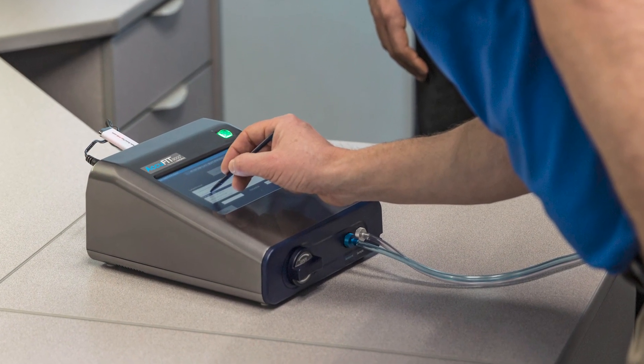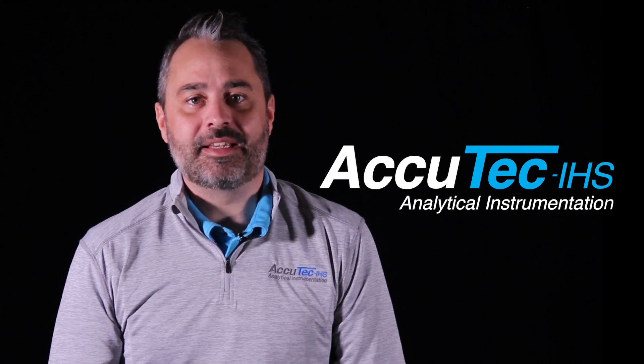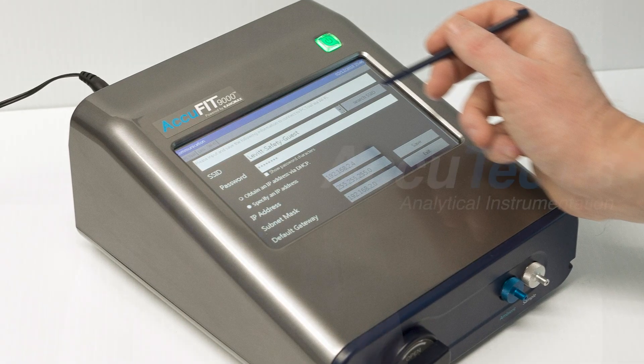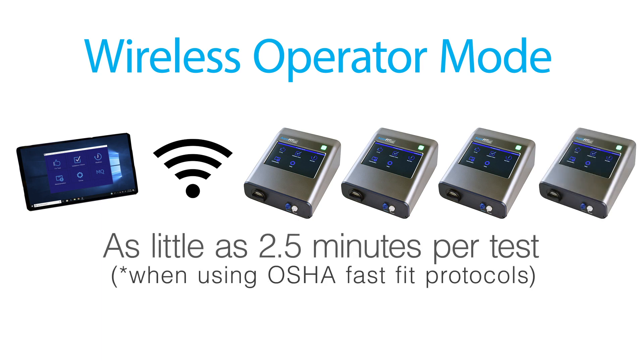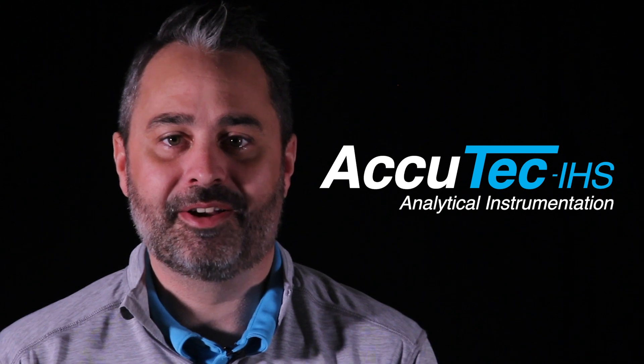To differentiate ourselves from our competition, we listened to the voice of the customer. Because of this, we were able to build in some exciting new features including standalone mode, built-in Wi-Fi, and some unique programming which allows us to be the first respirator fit tester on the market with wireless operator mode. Wireless operator mode allows a person to control one to four units with a tablet, with independent start and stop times, while still relaying instructions to the fit test subject on the built-in display on the instrument.